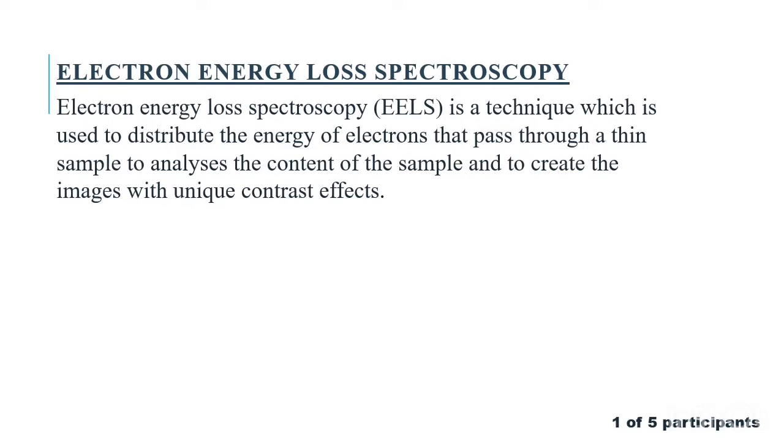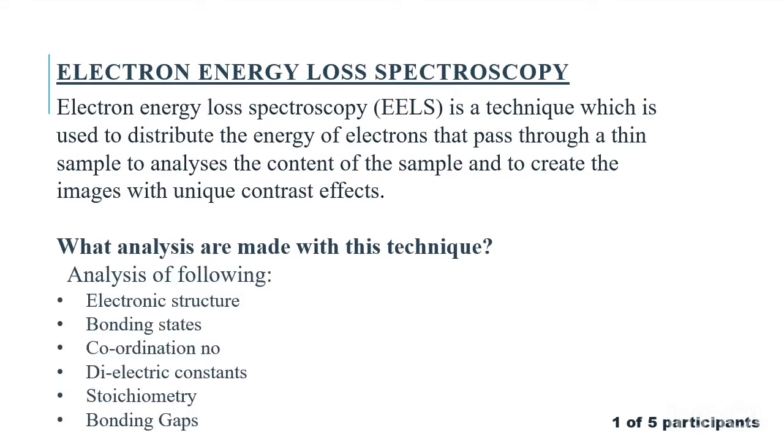This type of microscope uses high energy electrons, typically 60 to 300 kilovolts to interrogate the sample. The EEL spectrum contains a great deal of information. The analyses that can be made include electronic structure, bonding states, coordination number, dielectric constants, stoichiometry, bonding gaps, and many more.